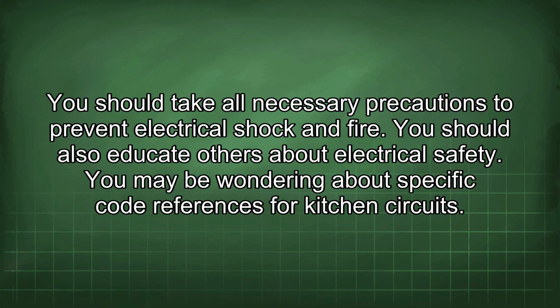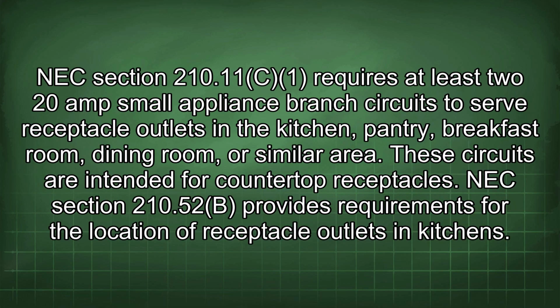You may be wondering about specific code references for kitchen circuits. NEC section 210.11 requires at least two 20 amp small appliance branch circuits to serve receptacle outlets in the kitchen, pantry, breakfast room, dining room, or similar area. These circuits are intended for countertop receptacles.